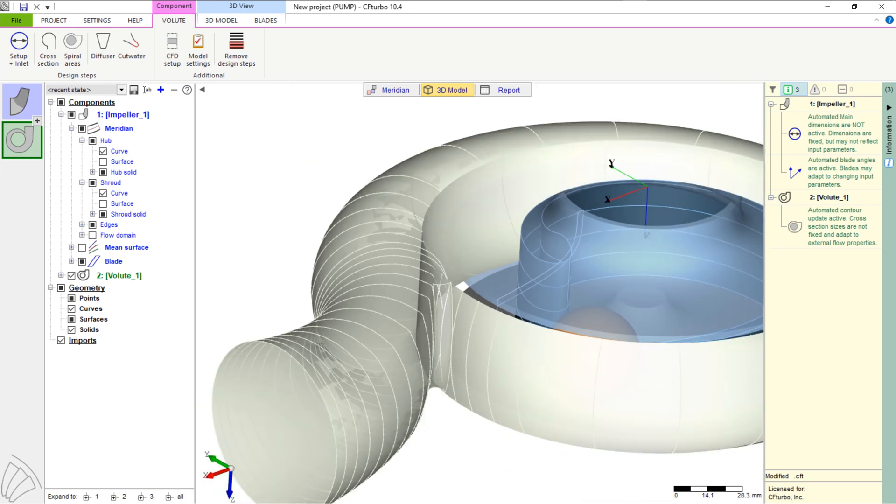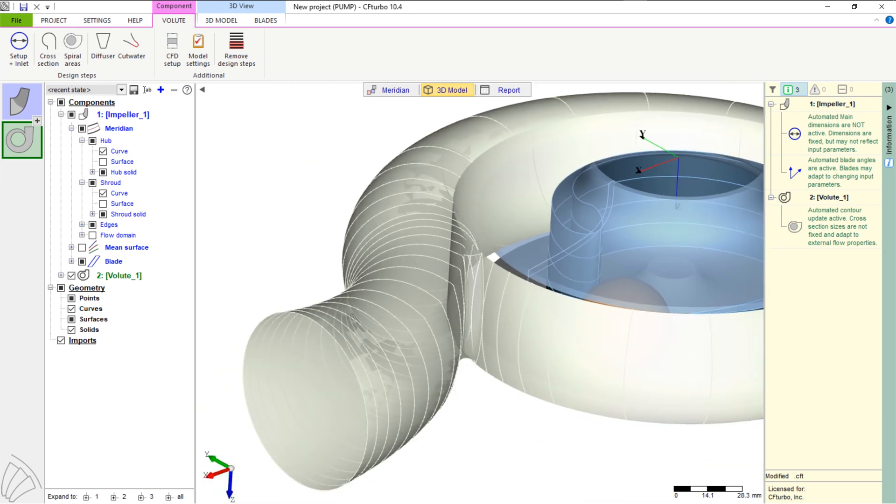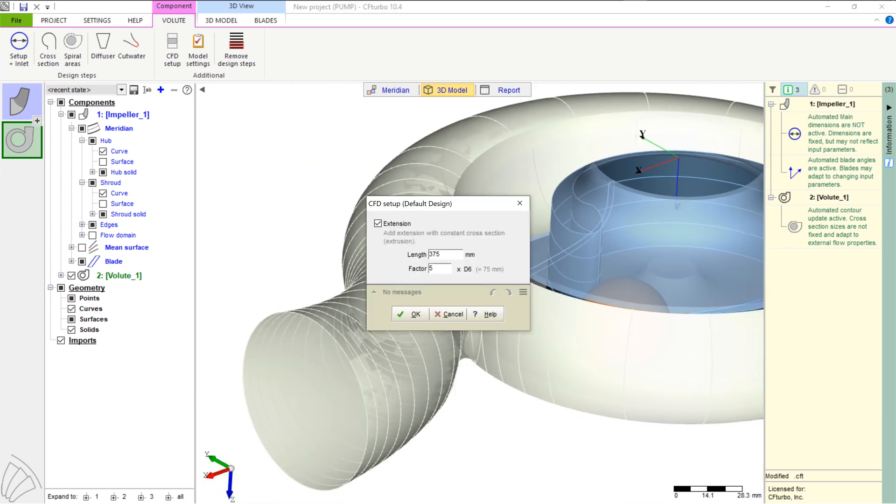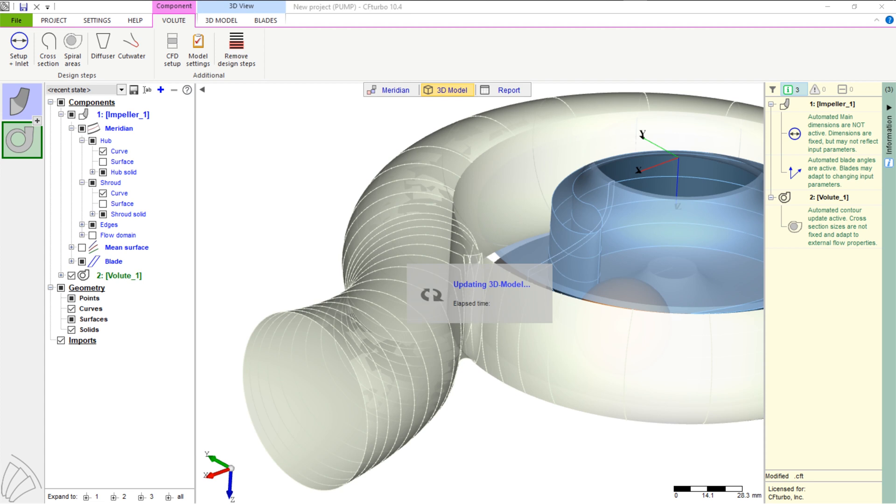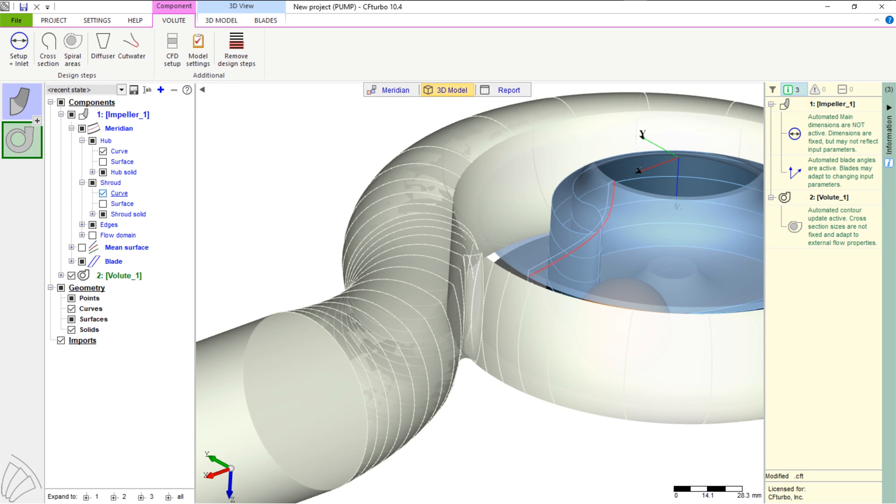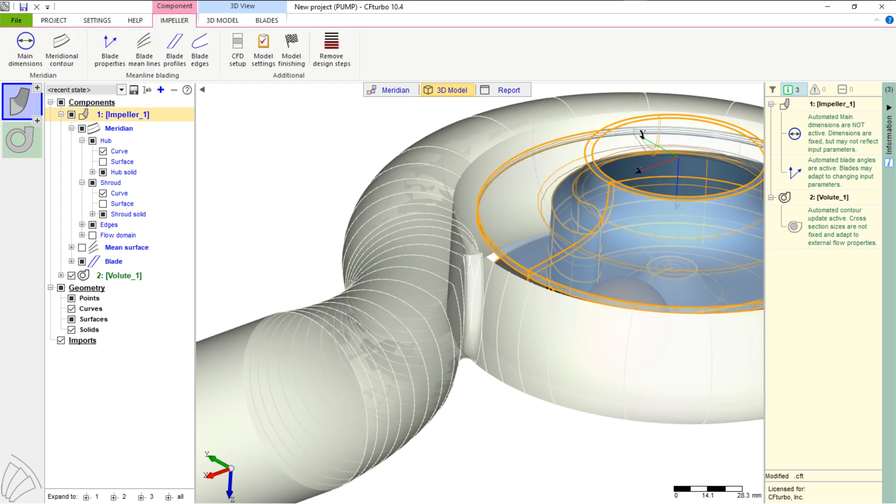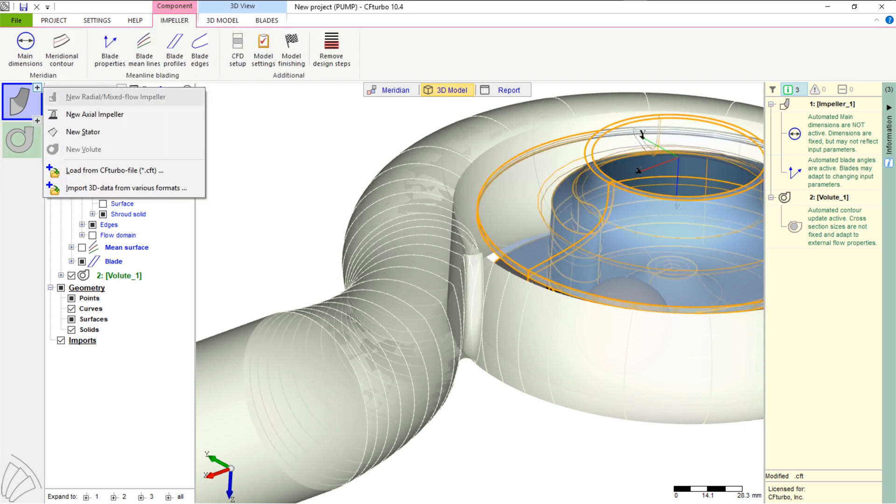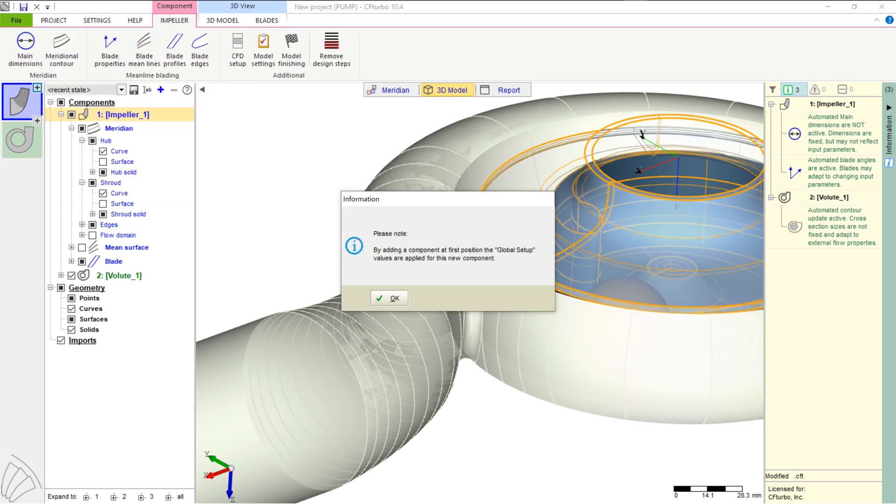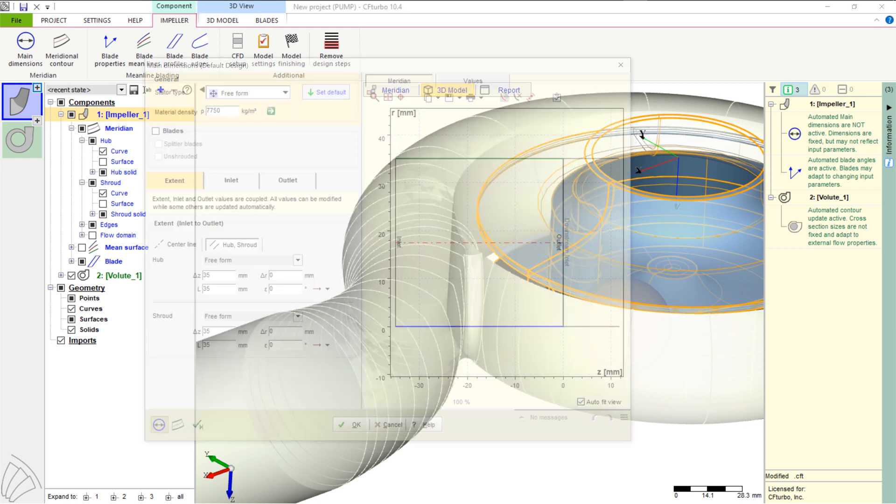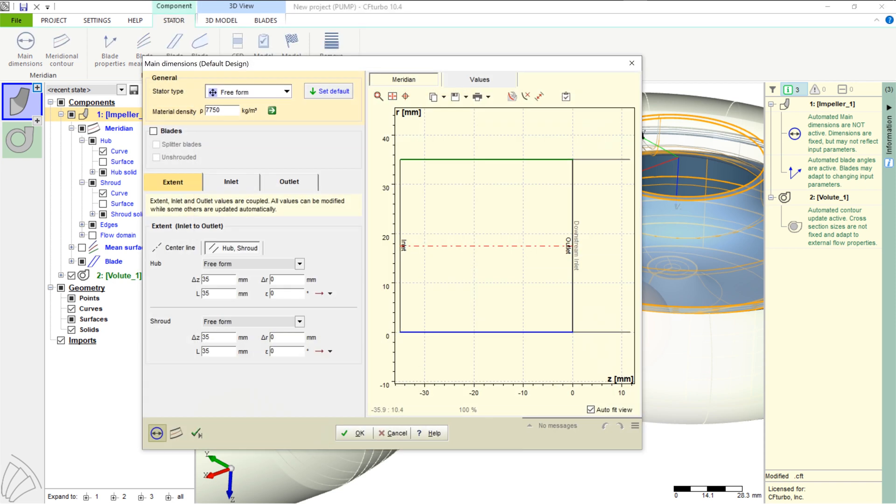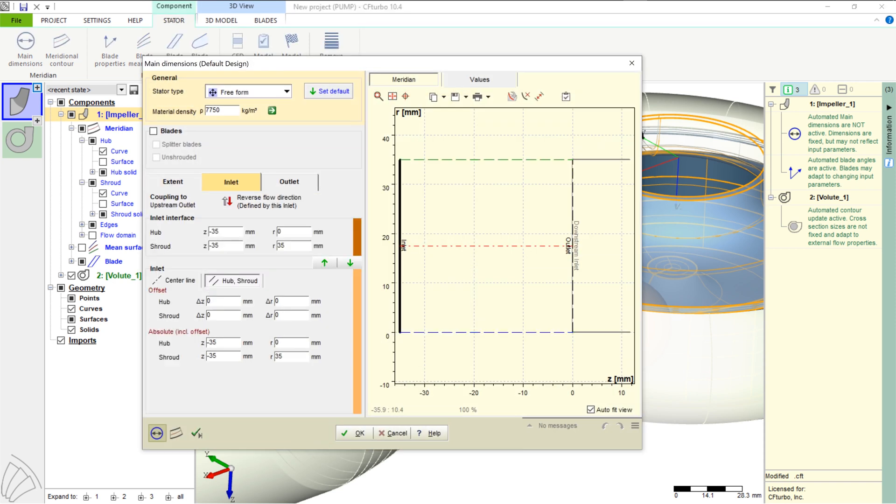To prepare the CFD model, we add an outlet extension downstream of the discharge diffuser. The outlet pipe should have an appropriate length in order to avoid a negative impact from the boundary conditions to the simulation results of the pump stage itself. We recommend an additional length of at least five times the discharge diffuser diameter.